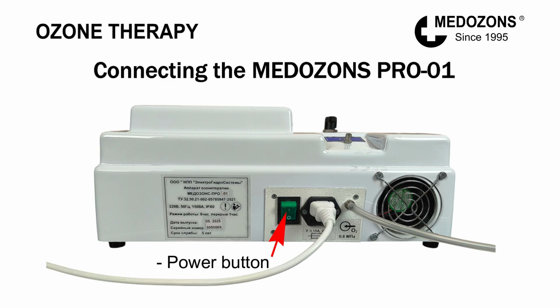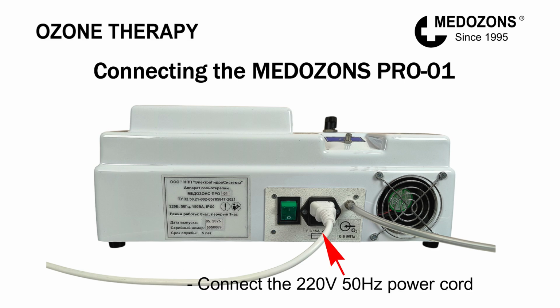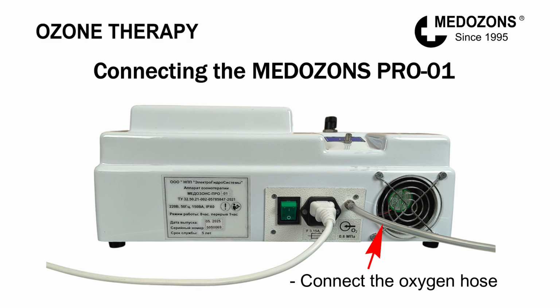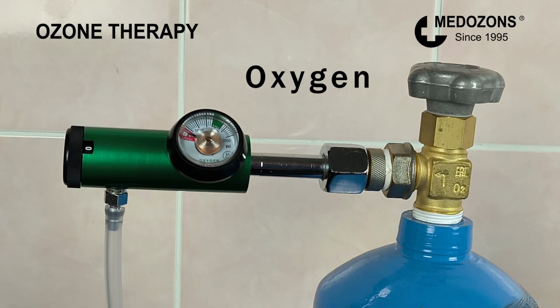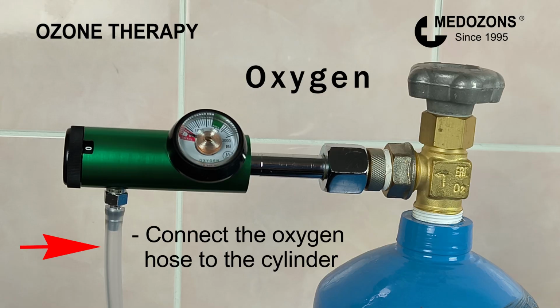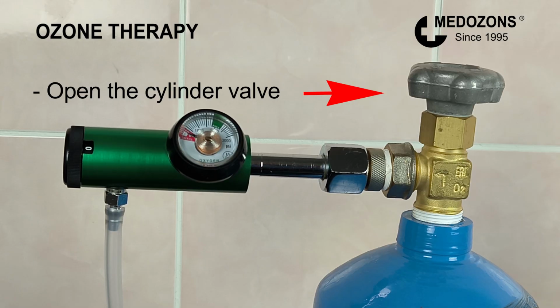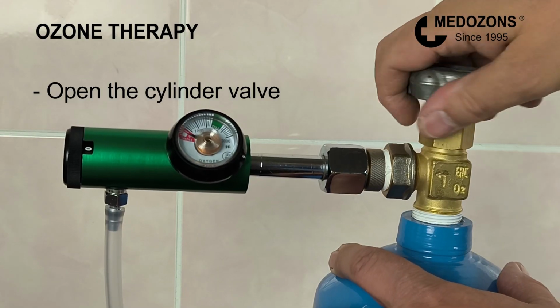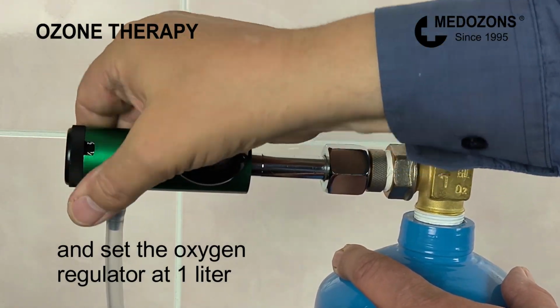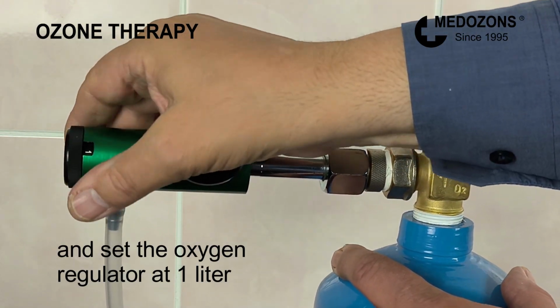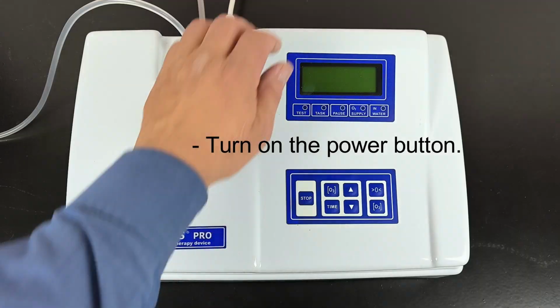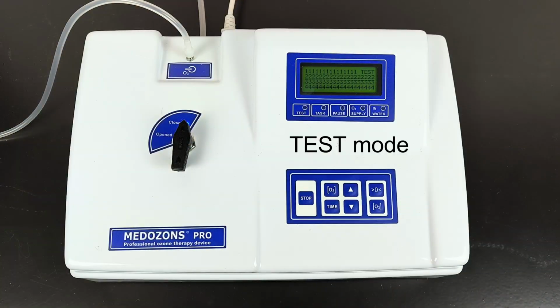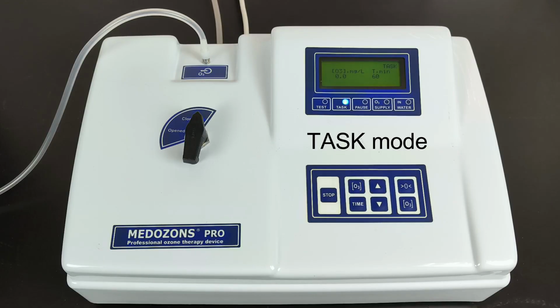Connecting the Medozons PRO-01. Power button. Connect the 220-volt 50 Hz power cord. Connect the oxygen hose. Connect the oxygen hose to the cylinder. Open the cylinder valve and set the oxygen regulator at 1 liter. Turn on the power button. Test mode. The device has entered task mode.